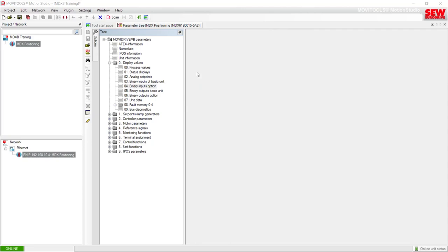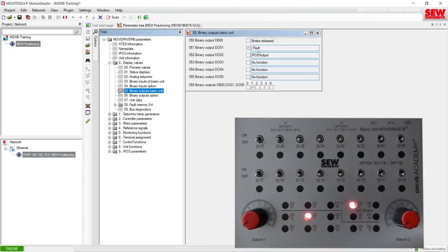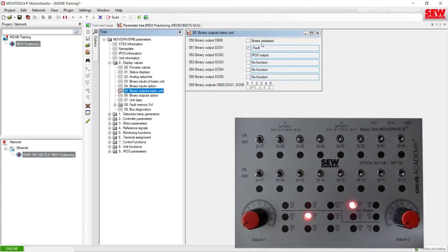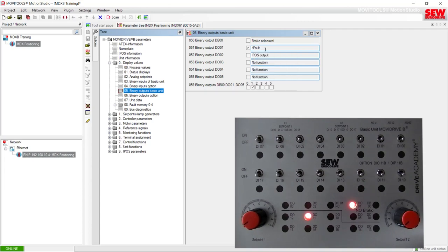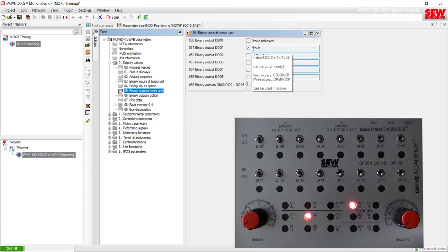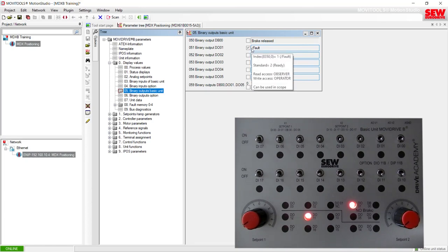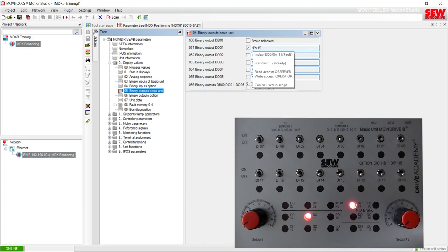Now we also have outputs. Item five is the binary outputs of the basic unit. Some of these digital outputs are configurable, but they will only give a value if it happens to be true. Currently the brake released signal, permanently assigned to DB00, is unchecked because the brake is not released since the drive is not enabled. The light for digital output 01 is currently on and there is a check mark here. The parameter assignment shows a slash before Fault — this slash means normally closed. So if the MOVIDRIVE is not faulted this output will be on, but if the MOVIDRIVE does fault, this output will go off.